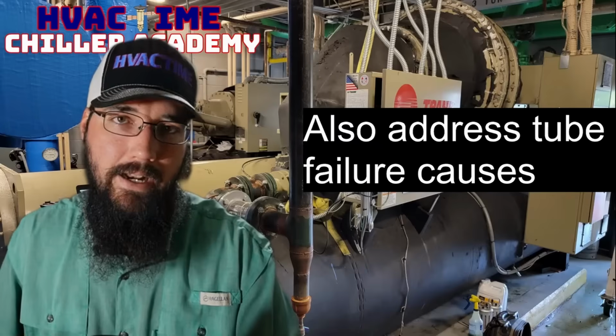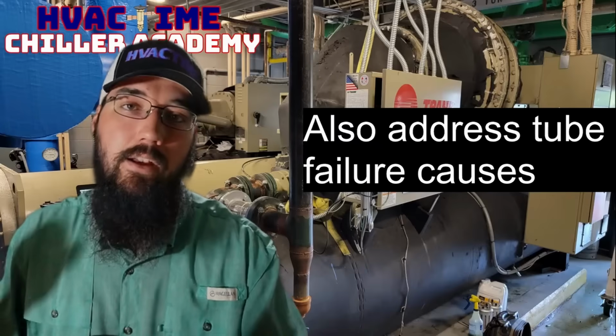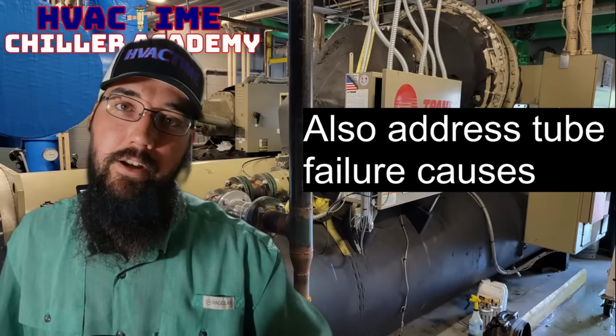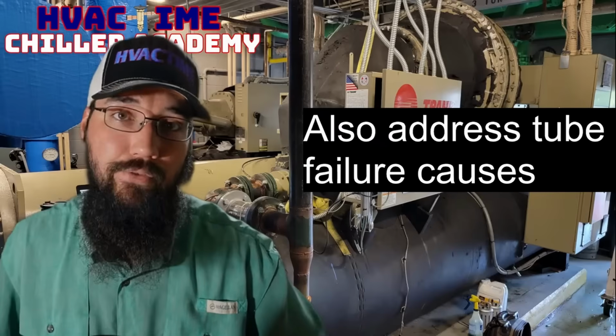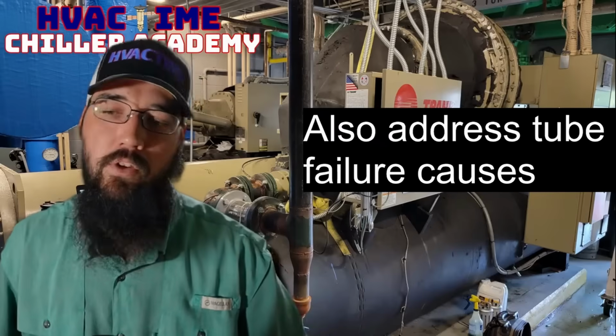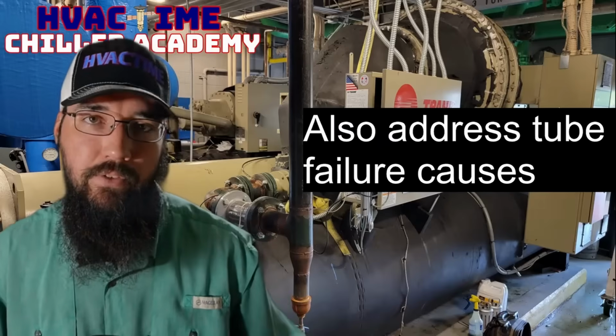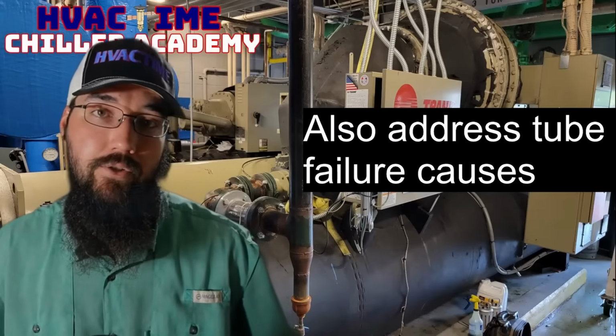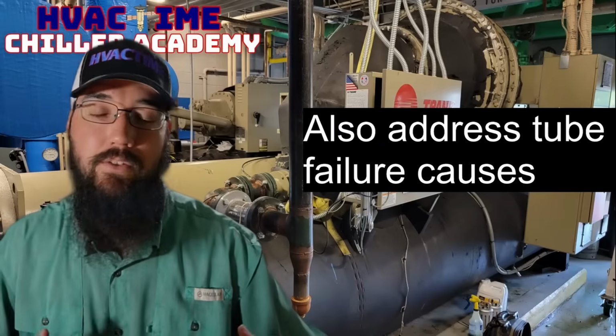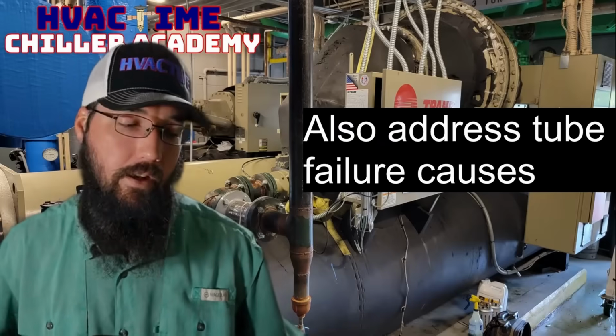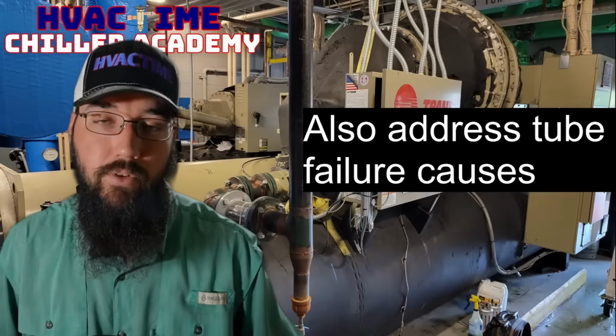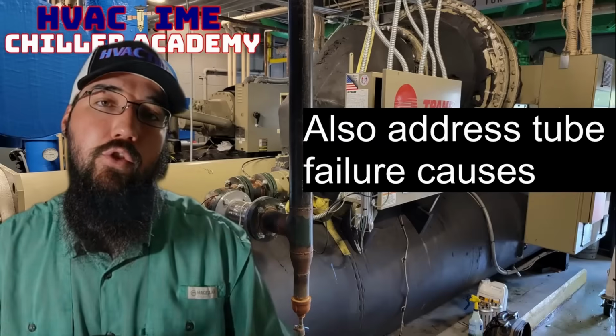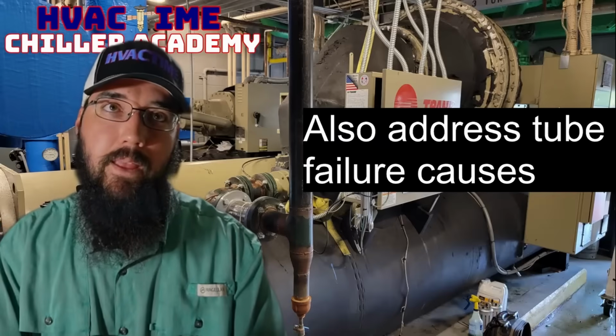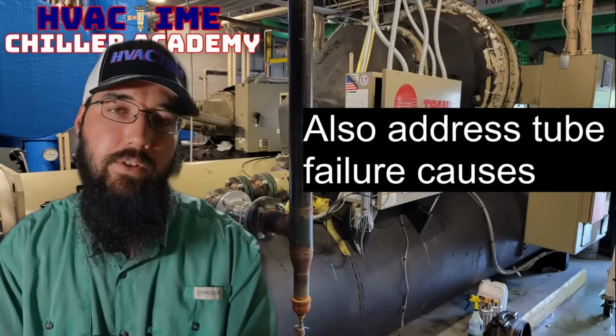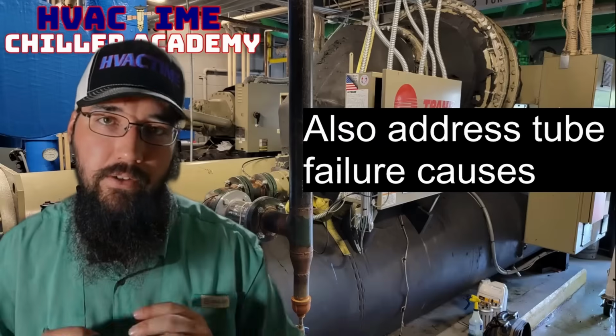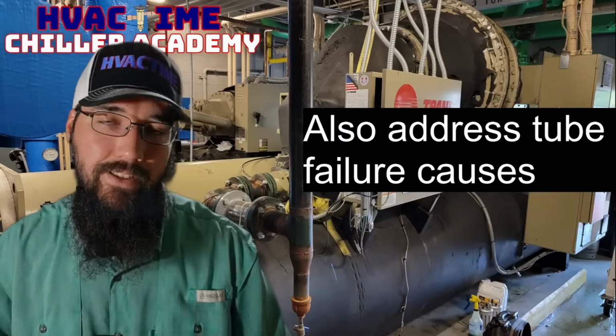and we never had an issue. So what we had happen was the freeze happened. A lot of properties had generators that were not properly maintained. They failed. Couldn't keep the pumps flowing, couldn't keep what heat trace we had working, and we had heat exchangers freeze up and bust everywhere. I mean, everywhere. It really wrecked us. So, the tubes freezing. The ones most susceptible to this would be a flooded or falling film design where the water is inside the tubes.